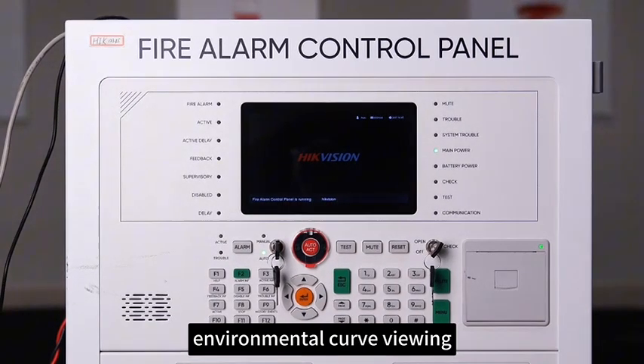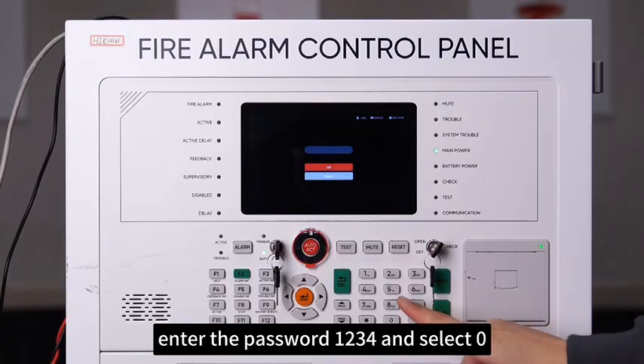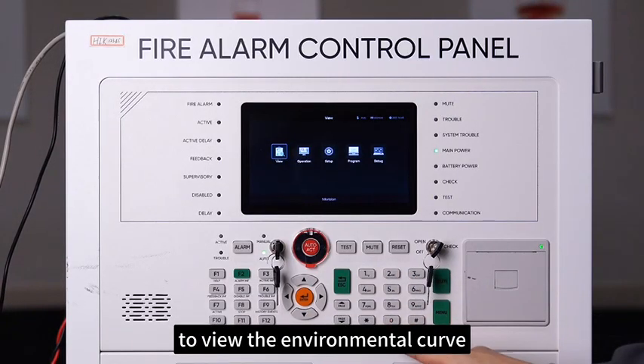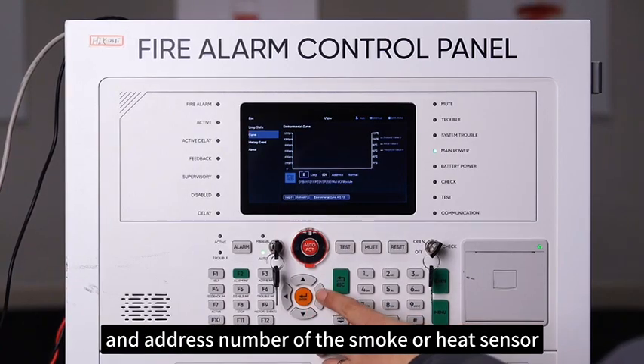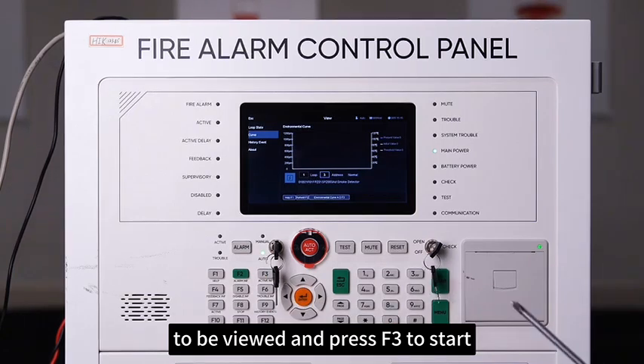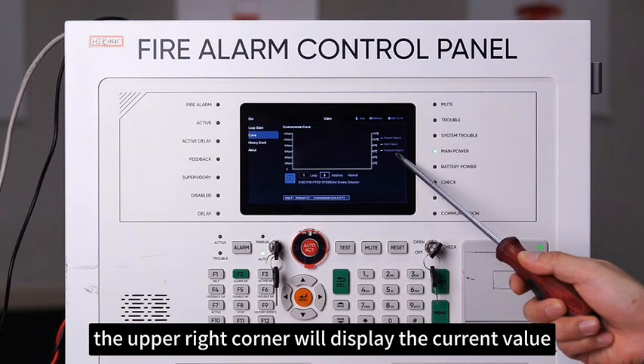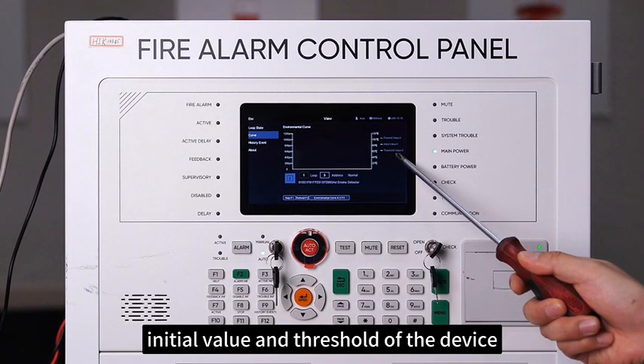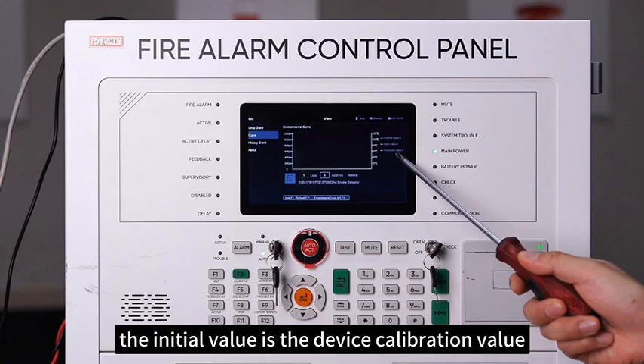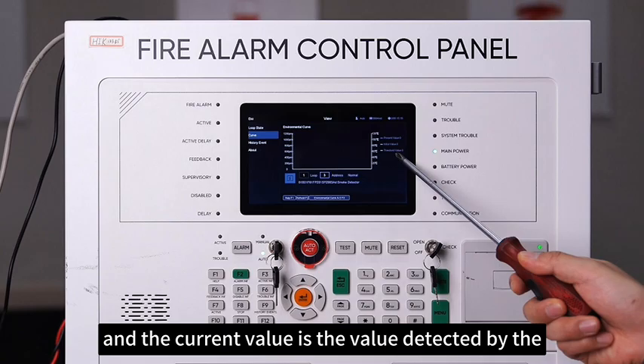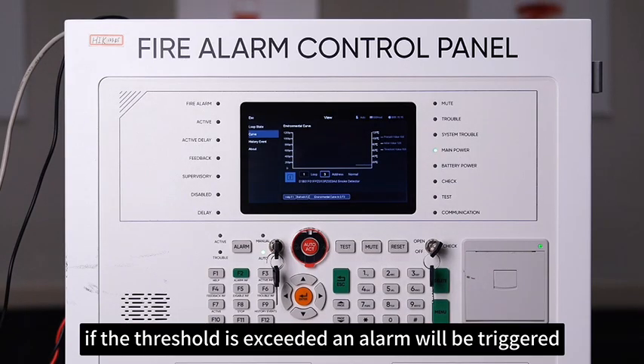Environmental curve viewing, press the menu key, enter the password 1234, and select 0 to view the environmental curve. Enter the circuit number and address number of the smoke or heat sensor to be viewed and press F3 to start. The upper right corner will display the current value, initial value, and threshold of the device. The initial value is the device calibration value, and the current value is the value detected by the current device. If the threshold is exceeded, an alarm will be triggered.